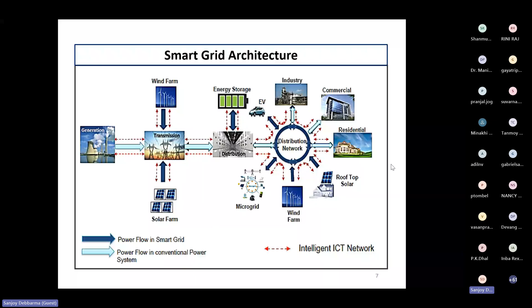Now, in an active distribution network, you'll find there will be lots of sensors employed, because without sensors, how do you visualize the entire network? There will be CTs, PTs, PMUs, and other microprocessor-based devices in the substations, giving you the entire picture of current, voltage, frequency, kilowatt-hour consumption, kilowatt generation, everything. Thereby you can decide whether the power flow at the distribution system can be managed optimally, while ensuring the grid limitations are not violated. The network constraints may be feeder limits, transformer limits, etc.